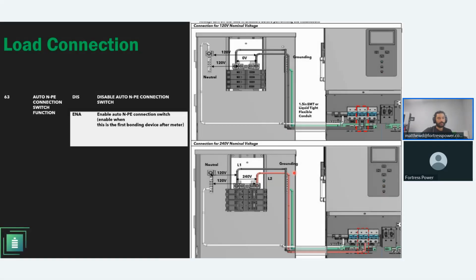And then the load output of the inverter would tie into a traditional main panel. Main panels, as standard for residential, come with 2 poles, where if you were doing a 120 volt single phase, then you can land each cable into line 1 and line 2 of that load panel, right? If you measure with your multimeter, you should measure 0 volts from line 1 to line 2, essentially, and then 120 volts from line 1 to neutral, right?